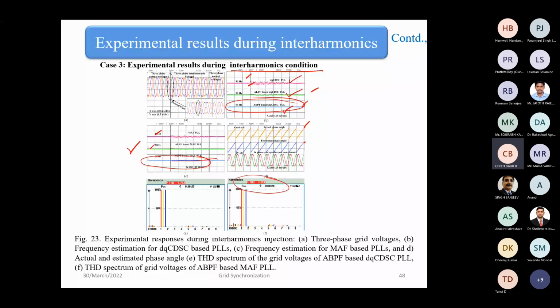These proposed PLLs are not only utilized for extracting the fundamental frequency and phase angle, but can also be used for grid monitoring. In the large spectrum of grid integration, this can also be used for grid monitoring and power quality improvement, by reducing or filtering out harmonic components present in the utility grid. With that, we are able to implement the control algorithm on the grid interactive power converter, so that successful integration of renewable power generation is possible.